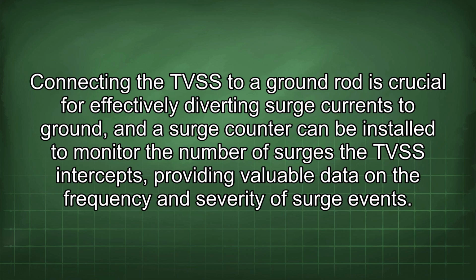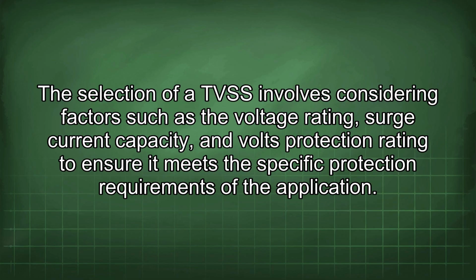Connecting the TVSS to a ground rod is crucial for effectively diverting surge currents to ground, and a surge counter can be installed to monitor the number of surges the TVSS intercepts, providing valuable data on the frequency and severity of surge events. The selection of a TVSS involves considering factors such as the voltage rating, surge current capacity, and voltage protection rating to ensure it meets the specific protection requirements of the application.